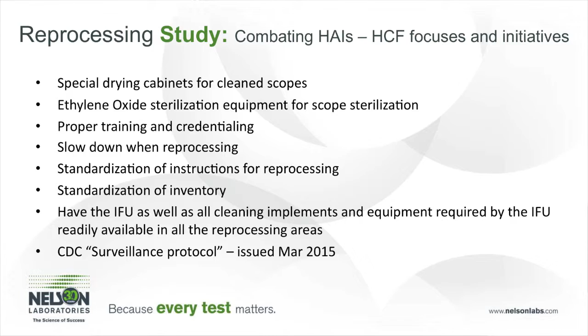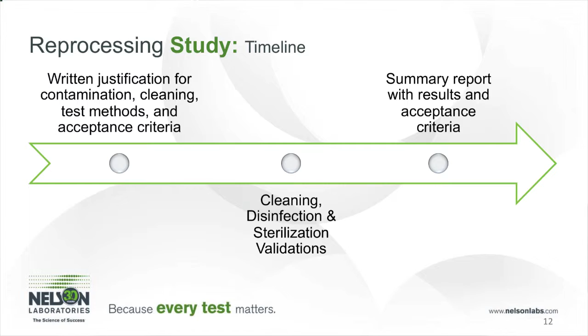So the one thing that's really important as you start the process of validation is the written justification for the cleaning, the contamination, the sterilization, and everything, and the acceptance criteria, and everything that goes along with a validation. We find most often that when the FDA asks questions to a medical device manufacturer, it's not because what they've done is incorrect, it's because the justification has not been complete, or it's not enough for the FDA to really determine that there was a thoughtful process going into the validation concepts. The next step are the validations, cleaning, disinfection, and sterilization of every reusable medical device. And then the summary report with results and acceptance criteria stating everything that is meeting the acceptance criteria.